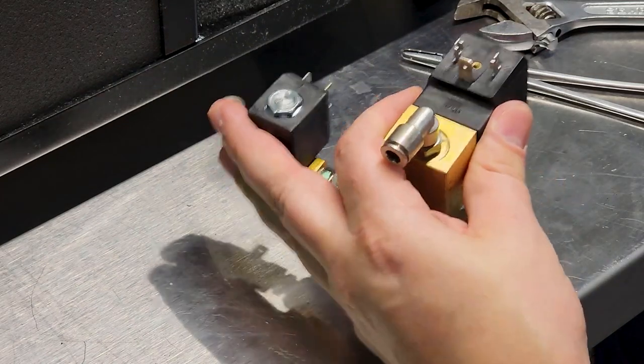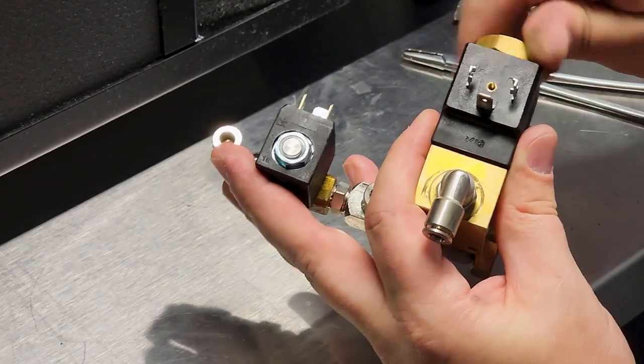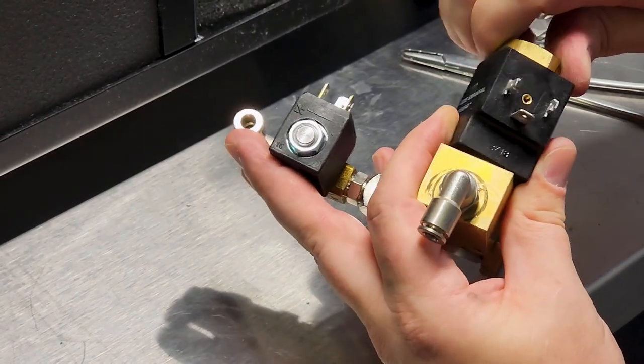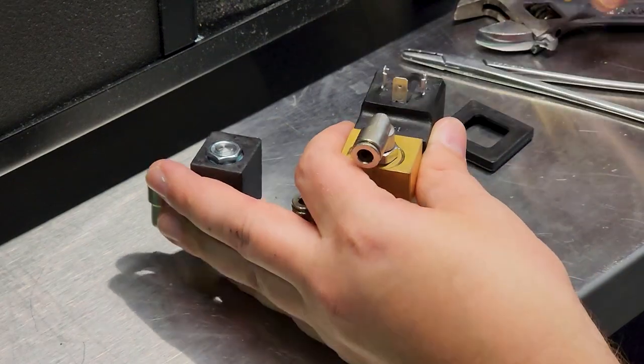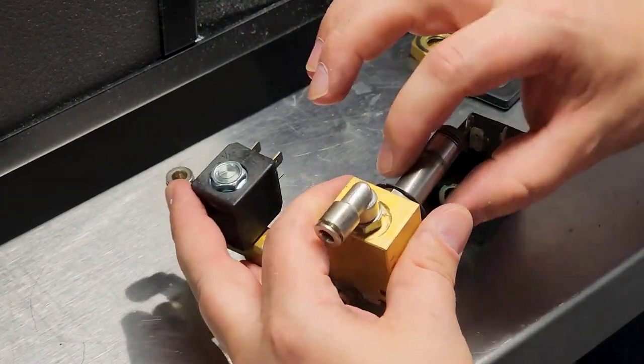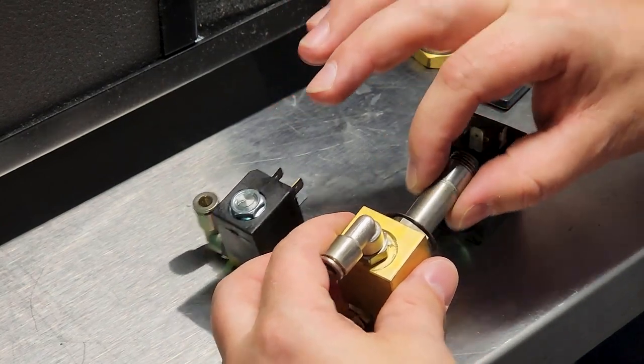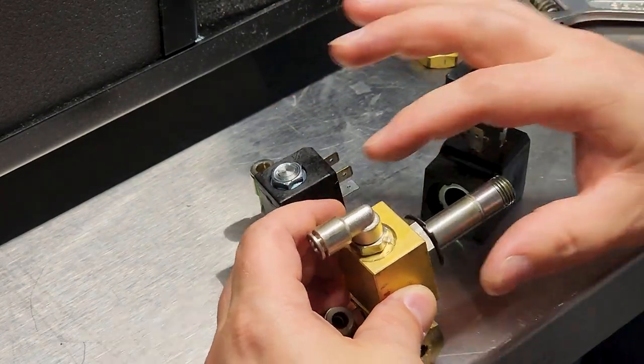Normally this guy has other protective features like a rubber cap and this dampening screw that's a retention screw because it's got an O-ring on there for dampening. So this guy is a defective solenoid and this slides off the valve body. This is the valve body right here that goes into a manifold block.